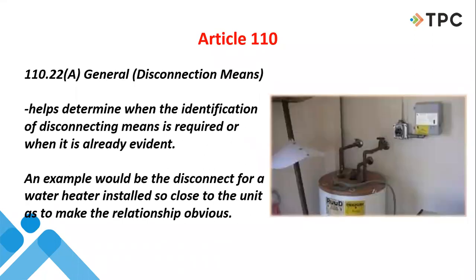This one, I'm all for anything like this that makes life easier. 110.22(A) is the one that requires a disconnect. But there's, call it an exception or whatever, that helps determine when the identification of a disconnect is required. In this case, you've got a hot water heater sitting there, disconnect right beside it. Pretty obvious why that thing's there. So they're just lightening up on the requirement that everything be identified. Sometimes you don't need an identification. It's painfully obvious just by what you're looking at why this thing is here, and they're allowing that to serve as such.